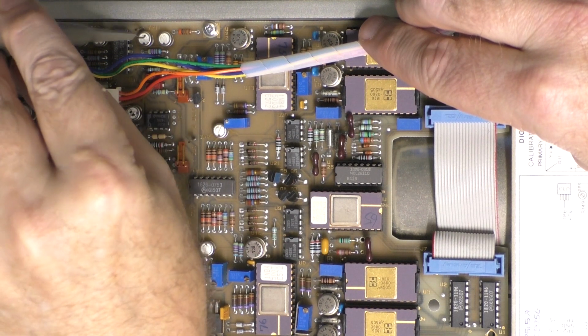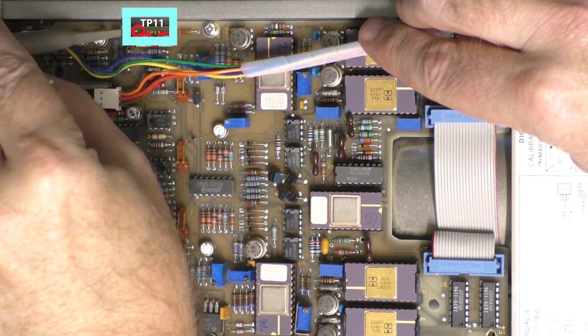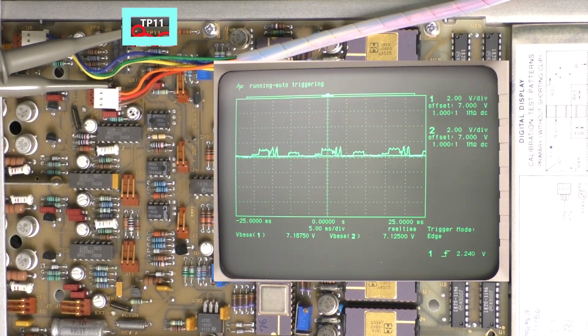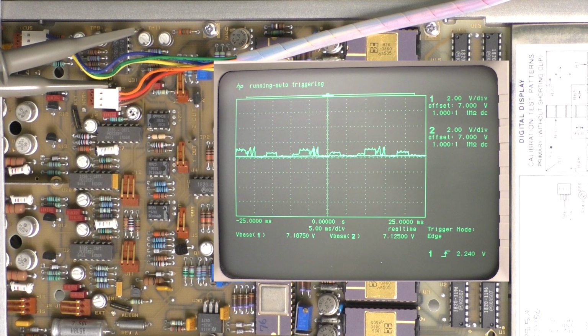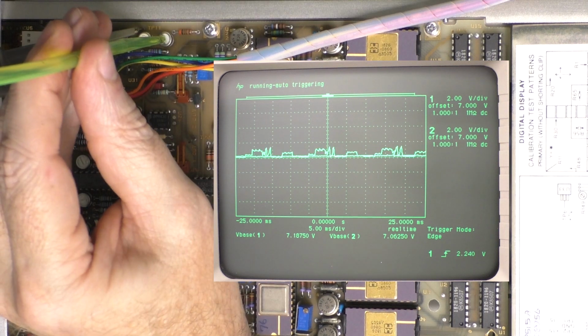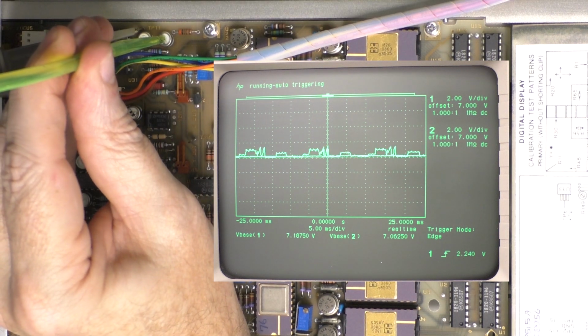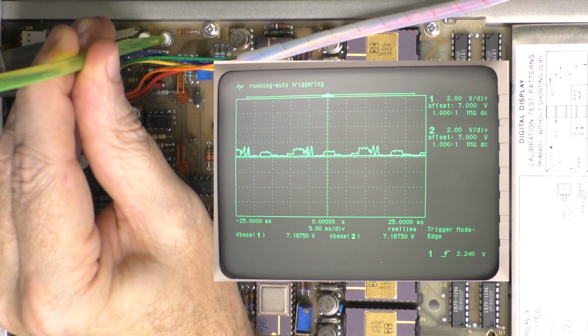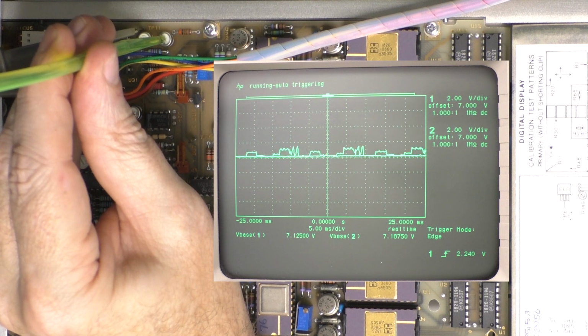Move the second probe onto test point 11 to monitor the X focus offset. Locate R135 on the A1 board. This adjusts the X focus offset. We need to adjust R135 so that the base voltage matches the base voltage at test point 9, 7.1875 volts.